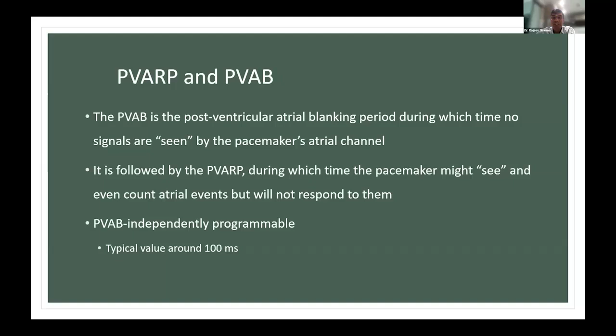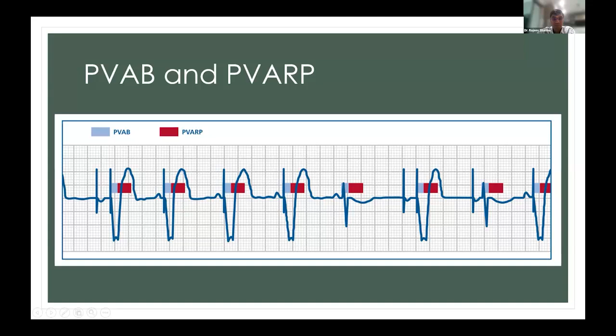Then there is the blanking period, this one. And in continuation of that there will be PVARP. If there is any activity here, it will not be sensed by the pacemaker. After that it will be sensed but will not be tracked. So blanking is the first portion of the refractory period. It is after atrial pacing as well as after ventricular pacing.